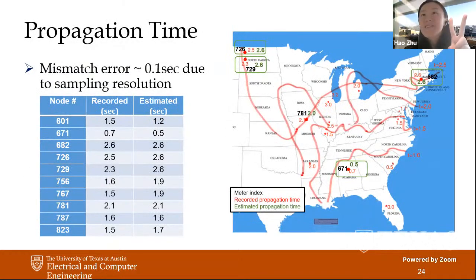So from that, I know how it goes from one location to the other. I only need to pick the 2 data streams from these respective locations. But if I want to know how it happens for this whole eastern interconnection, then the more the merrier. So usually we say that this behavior changes like 500 miles per second. So maybe like a radius of 500 miles, or even lower than that. The coverage in that order is good.